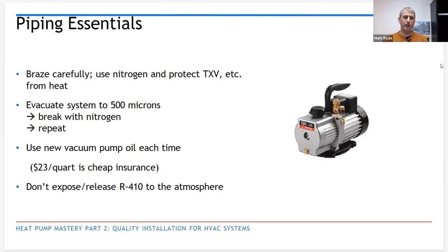A good evacuation, a triple evac, again, consult the manual. There's varying levels as to how deep of a vacuum they want you to pull and for how long. New vacuum pump oil each time. That's, as the slide here says, good cheap insurance. A quart of oil is $23, and it'll ensure a good dry vac each time you do that.